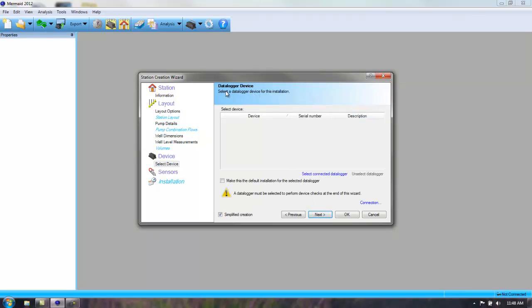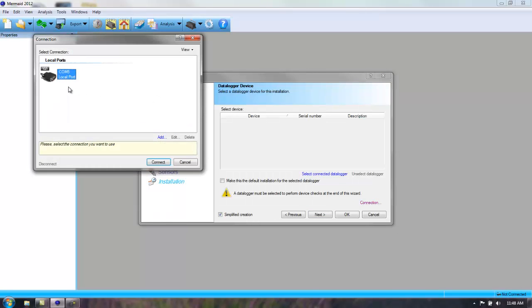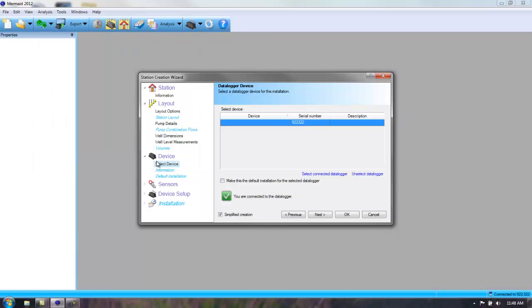At this point, to do the data logger device, you need to connect to the particular data logger you're going to be using. So down at the bottom right hand corner it says it's not connected. So I'm going to go to Connections, and it brings up the port that I'm going to use. Press Connect. If you notice, the serial number is now in the window as well as down in the bottom right hand corner. Then press Next.